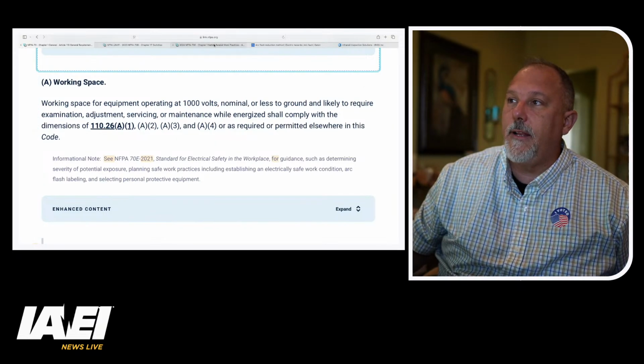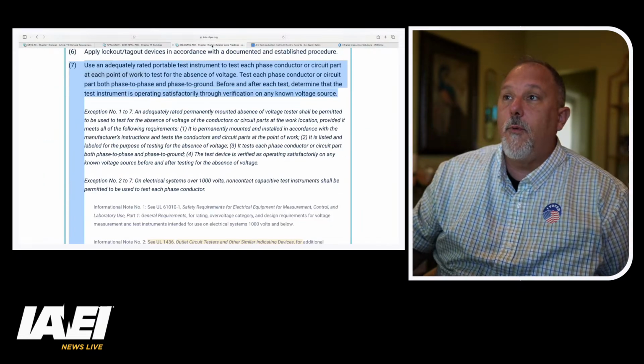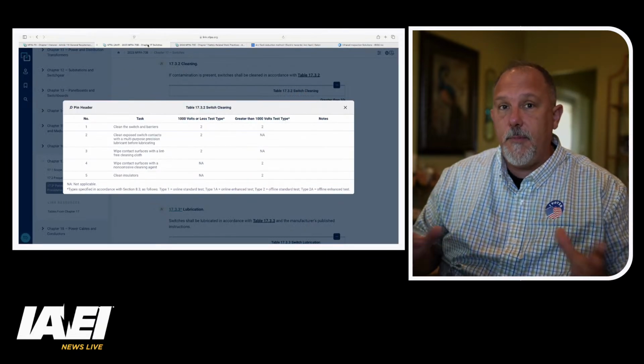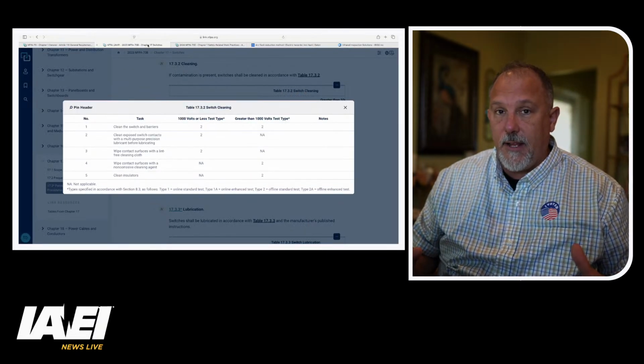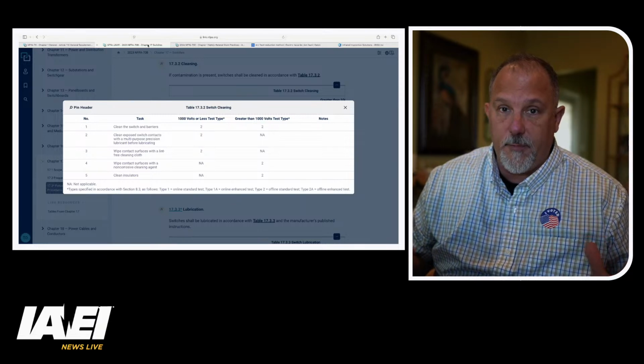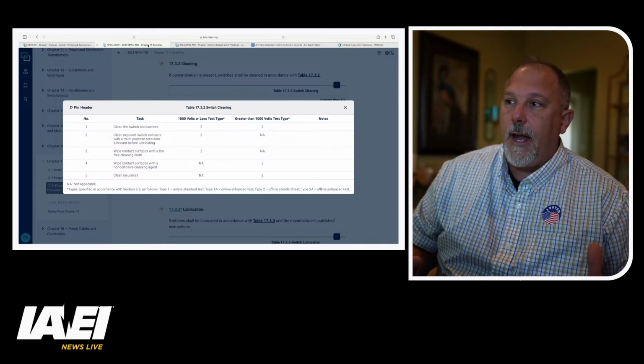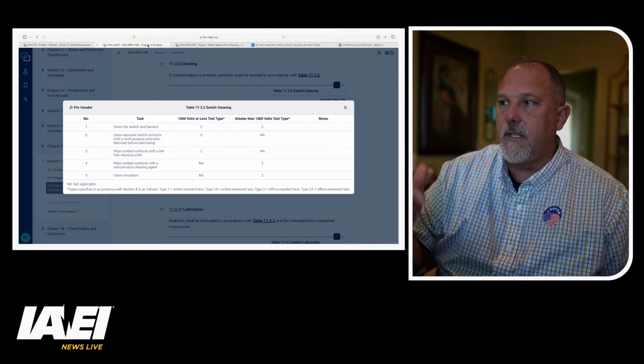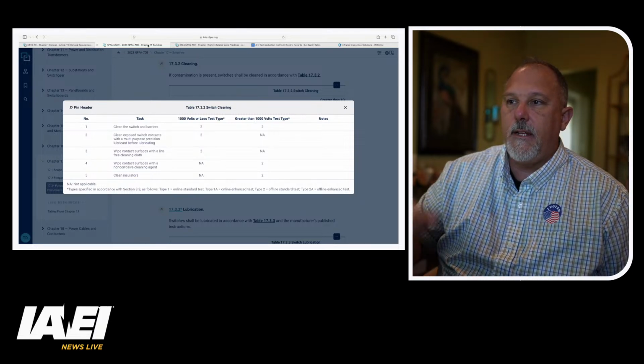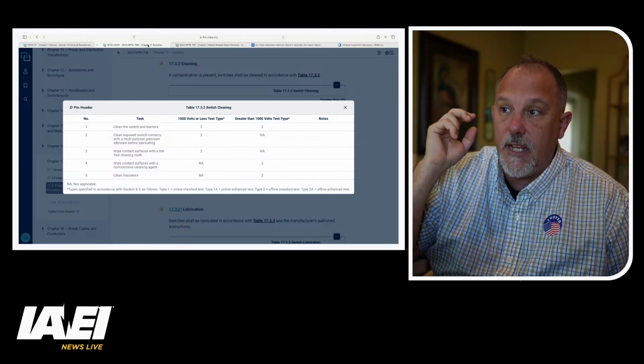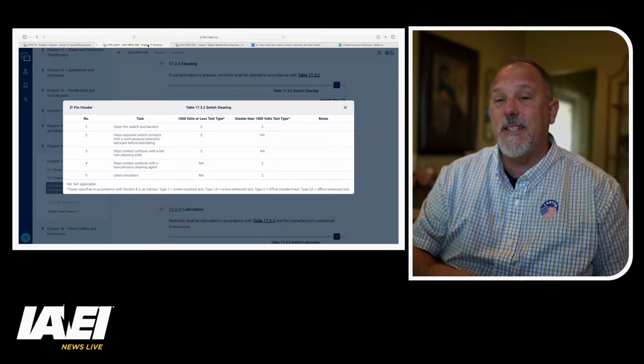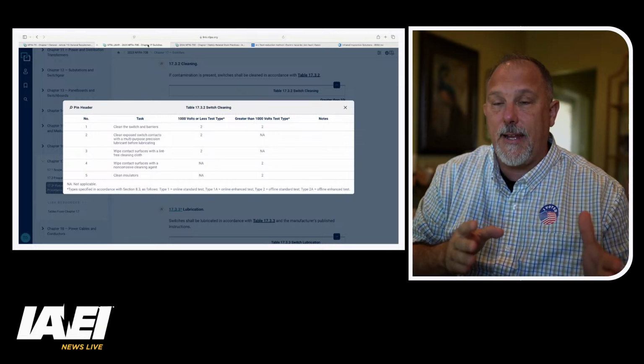When I look at 70E, and when I look at 70B, so I've got three documents open here on NFPA Link, which is another value for NFPA Link. I look at 70B and it says I need to clean this thing. I need to clean the switch, the barriers. I have to clean the exposed switch contacts. That means I got to open that door and get inside.